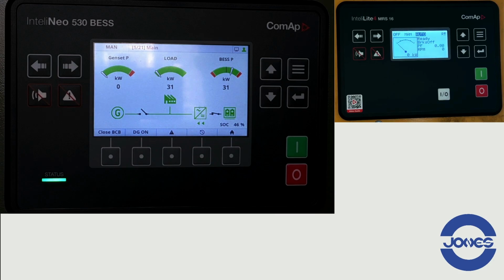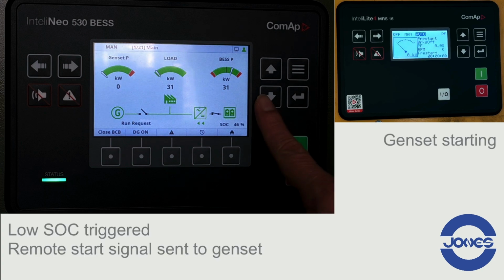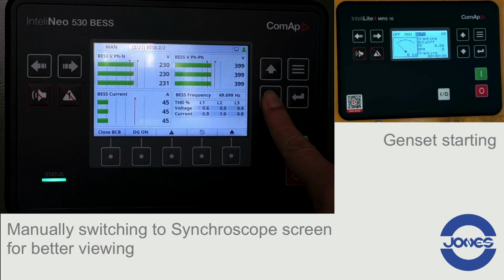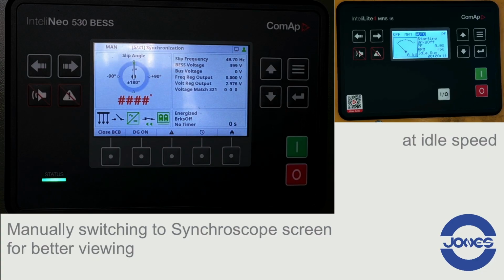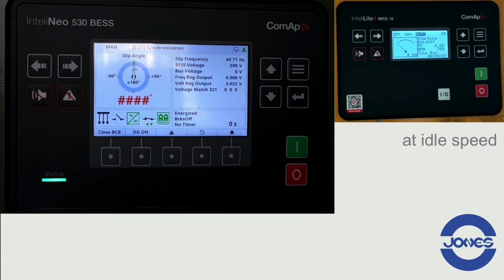Because we don't want this demonstration to be too long, we have simulated a situation where the low SOC is triggered. So, we have low SOC triggered and a remote start signal is sent to the genset. I'm manually switching to the synchroscope screen for better viewing. On a running system, you don't need to be switching to the synchroscope screen. The system will still auto-sync. The genset has started, now at idle speed and ramping up to run speed.